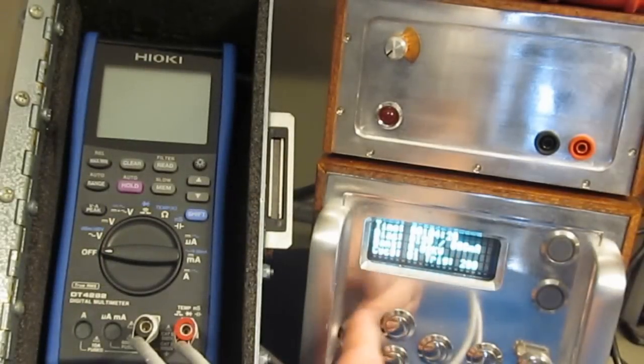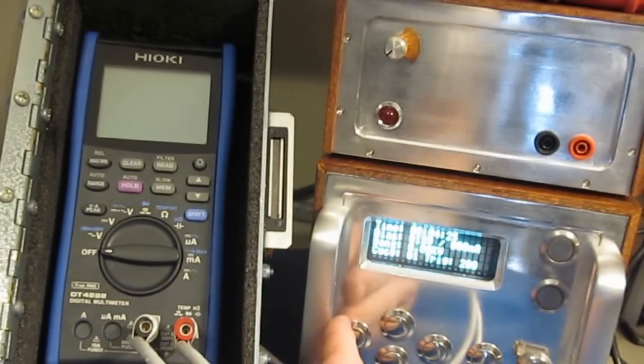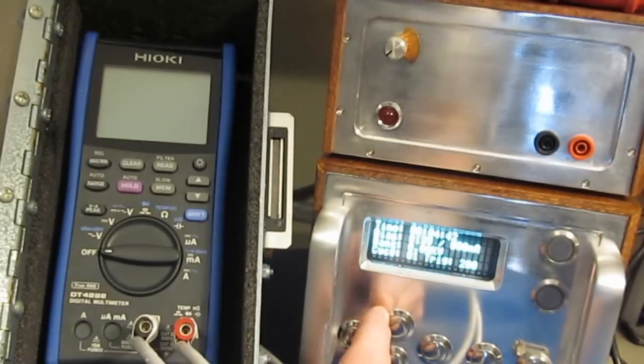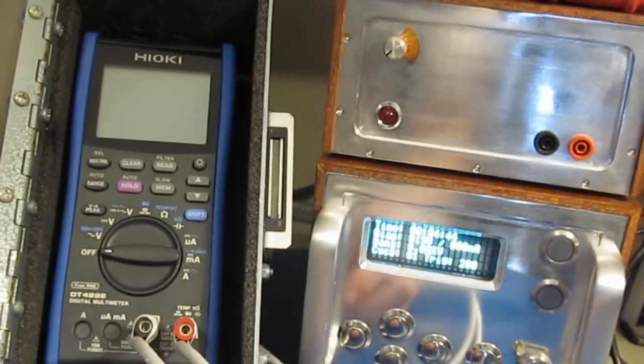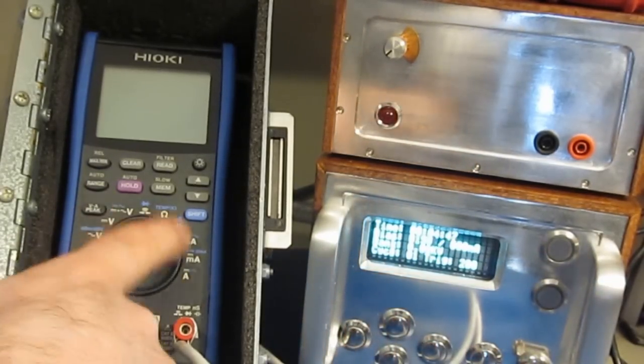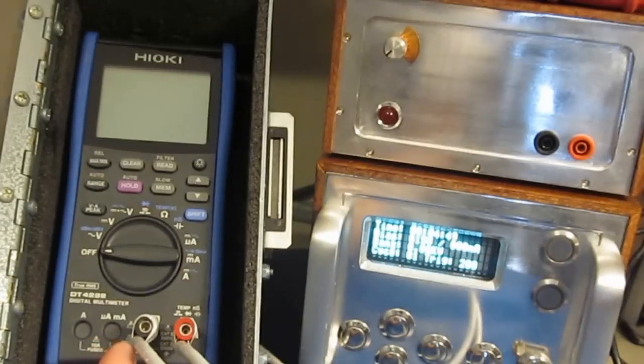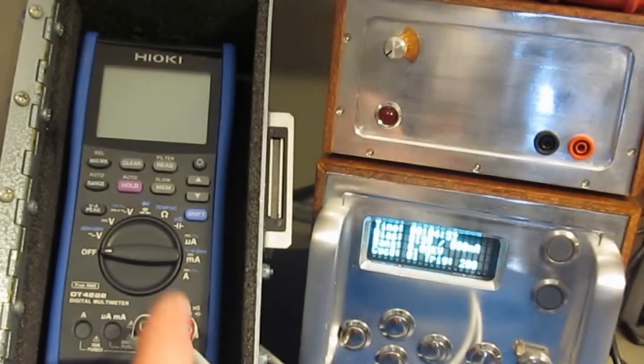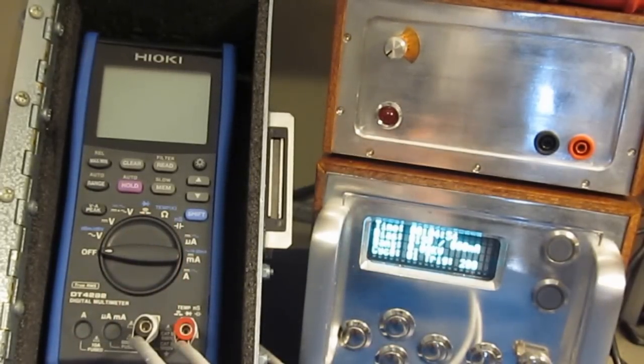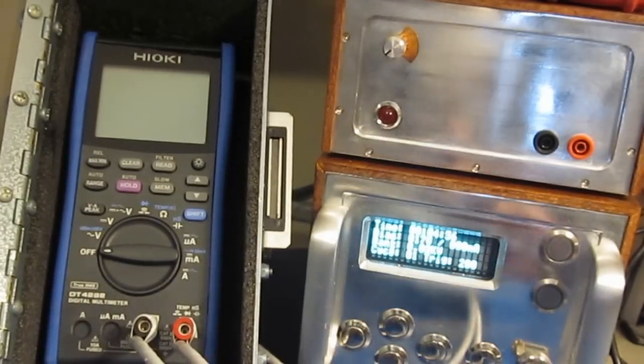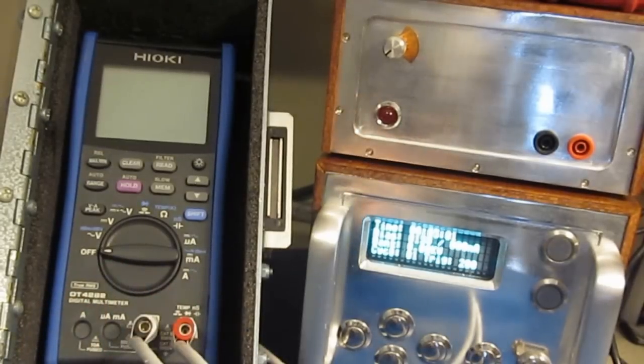Next we're going to be applying transients to the meter using our transient generator here. Again, this is a custom made generator. We're going to apply 5 transients, both positive and negative, with the meter set to each mode, and then we're going to functional test it. Again, this is an exponentially decaying waveform, and I want to be clear, I've had various people suggest that I was essentially just hooking these up to a capacitor bank. Again, that's not at all the case.